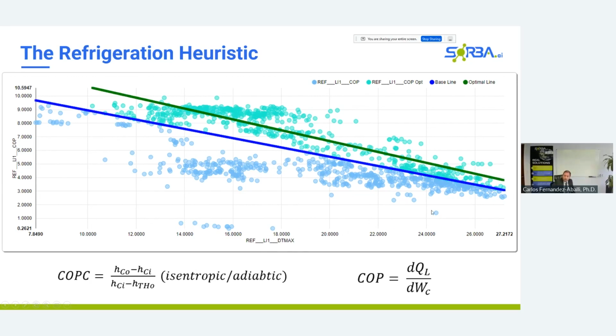What the APC is doing is saying, okay, so what's my average performance? And saying anything above average is good behavior. And it is setting the control set points, so what is controllable, the control variables in your system, to operate like the green line. And in this case, we're seeing an improvement, say, around here from 6 to 8. So that's almost a 30% improvement in performance in this particular case.